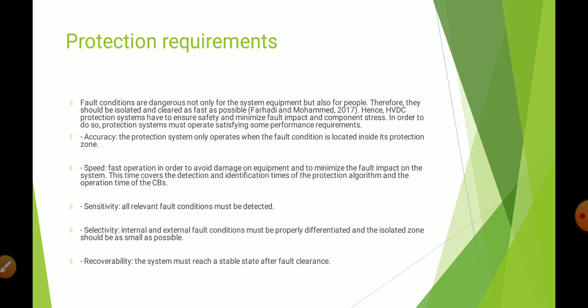Protection requirements. Fault conditions are dangerous, not only for the system but also for people. Therefore, they should be isolated and cleared as fast as possible. Hence, the HVDC protection system has to ensure safety and minimize the fault impact and component stress. In order to do so, the protection systems must operate satisfying some performance requirements: accuracy, speed, sensitivity, selectivity, recoverability. These are some protection requirements that it must follow.